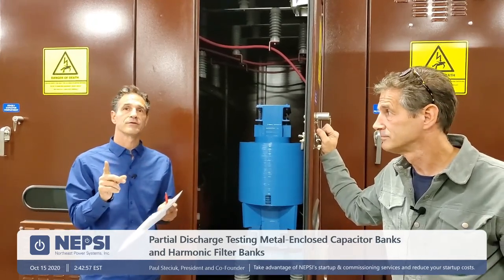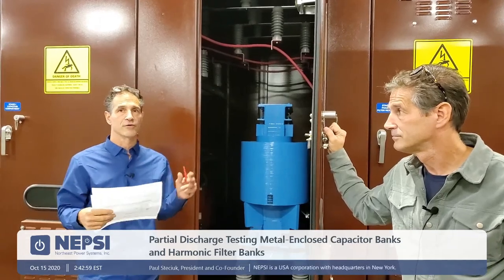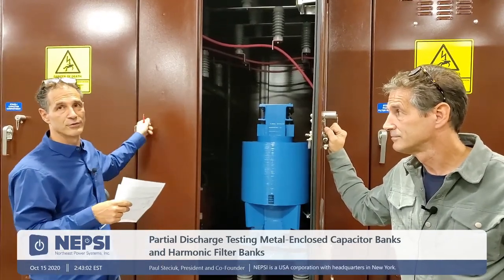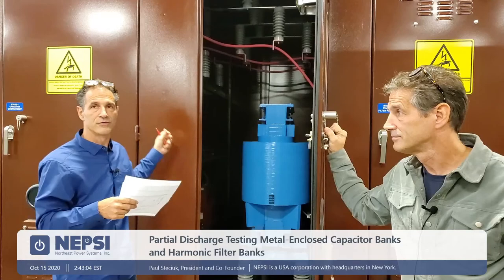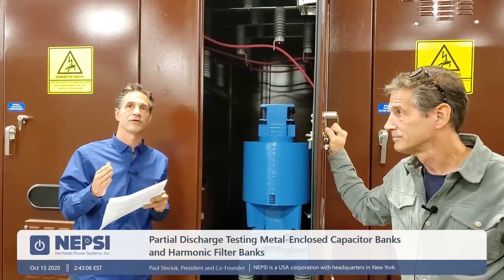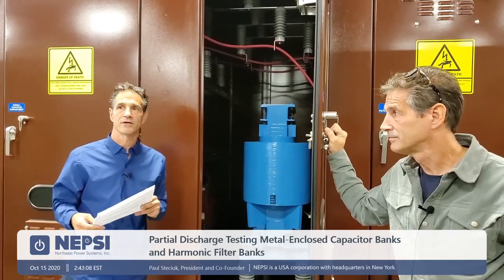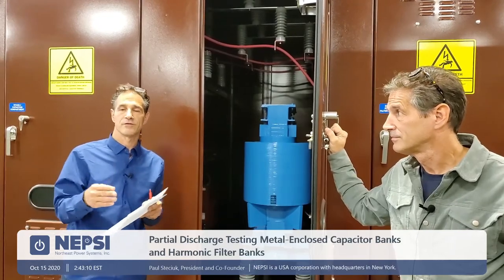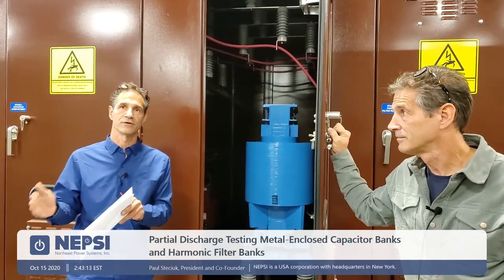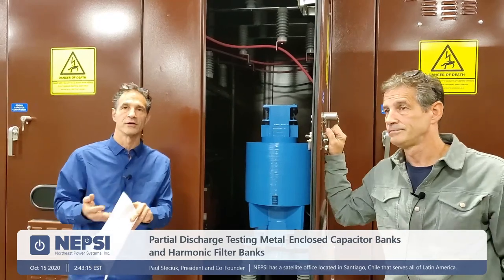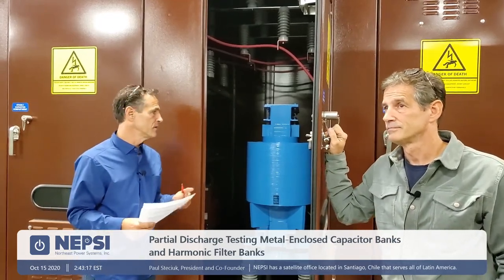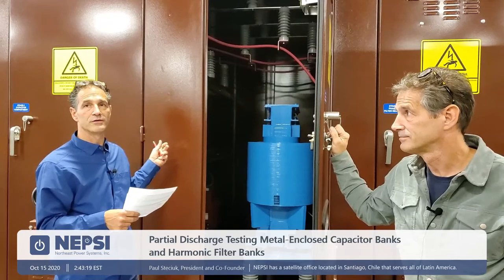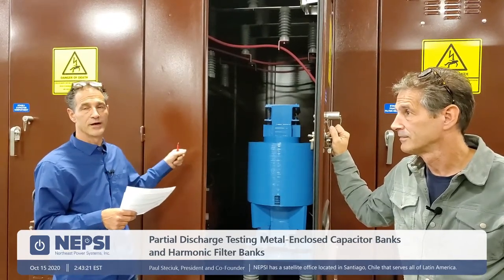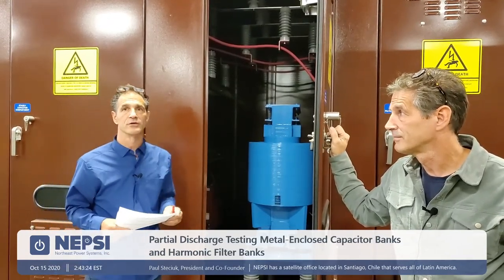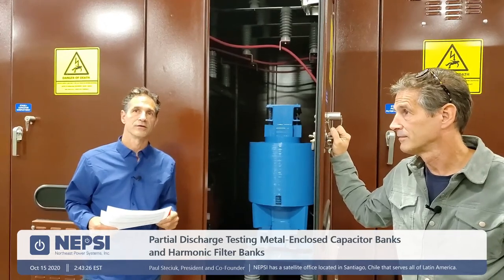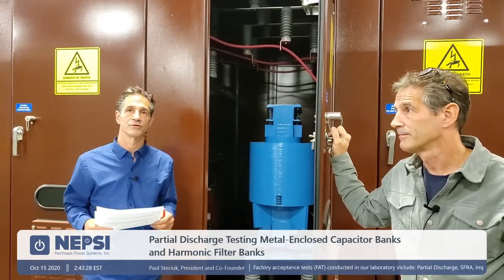And the worst thing to think about is that the failure occurs when somebody's doing a switching operation. It just so happens that it's usually a switching operation, a transient, that will bring out a defect in a system that has been degraded over time because of partial discharge, tracking or treeing, something like that. The condition will most likely result in flashover when the guy is switching. So it's really an arc flash hazard that you want to avoid, and you want to prevent partial discharge.